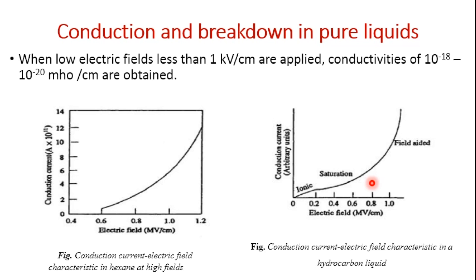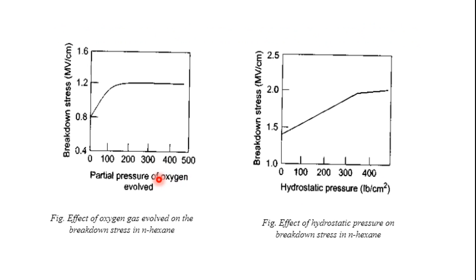The breakdown voltage mainly depends on the field, gap separation, work function of the material, and temperature of the cathode. In addition, liquid viscosity, temperature, density, and the molecular structure of the liquid also influence the breakdown strength. It has been observed that the increase in breakdown strength is greater if the dissolved gases are electronegative in nature — from the partial pressure of evolved oxygen. Similarly, increasing the hydrostatic pressure of the liquid increases the breakdown strength.